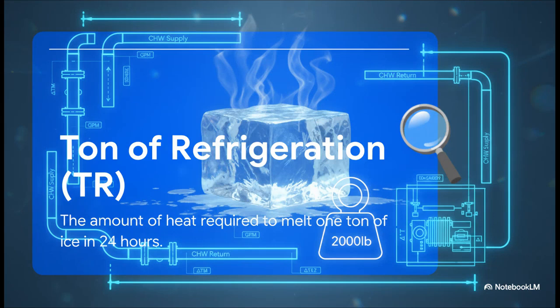Okay, before we get our hands dirty, we've got to speak the language. And the most fundamental unit we have is the ton of refrigeration, or TR. It's such a cool, kind of old-school term, but it perfectly captures what we're doing. We're removing enough heat from a space to melt a literal ton of ice. This is how we measure the raw, brute force power of our system.